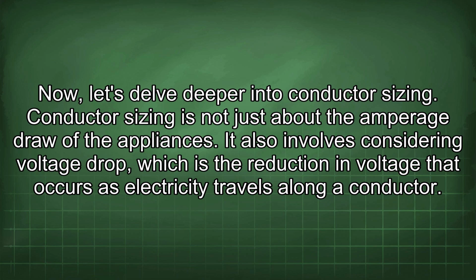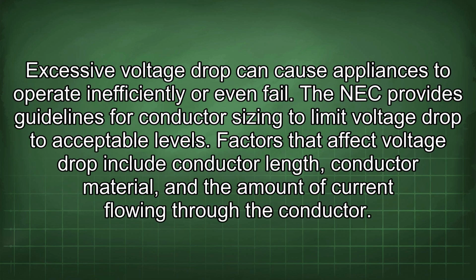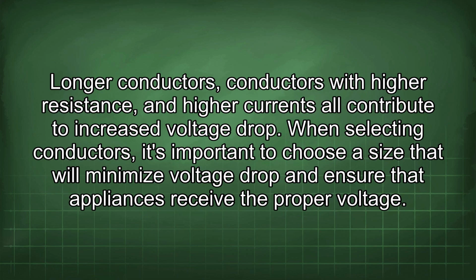Conductor sizing is not just about the amperage draw of the appliances. It also involves considering voltage drop, which is the reduction in voltage that occurs as electricity travels along a conductor. Excessive voltage drop can cause appliances to operate inefficiently or even fail. The NEC provides guidelines for conductor sizing to limit voltage drop to acceptable levels. Factors that affect voltage drop include conductor length, conductor material, and the amount of current flowing through the conductor. Longer conductors, conductors with higher resistance, and higher currents all contribute to increased voltage drop. When selecting conductors, it's important to choose a size that will minimize voltage drop and ensure that appliances receive the proper voltage.